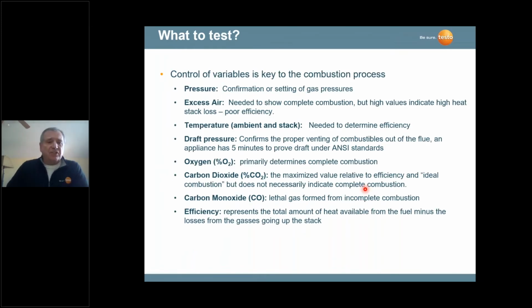So, there are things that we can control. We control variables in the combustion process, and pressure is a measurement that we take: the fuel pressure, as well as draft in the stack. We do a calculation called excess air. We measure temperature through a thermocouple that's at the probe tip. We also measure the ambient temperature. We can measure pressure not only from a positive side, but a negative side, so we can measure the draft. Percent oxygen is very important. We talked about complete combustion. We need to see oxygen when our probe is in the stack.